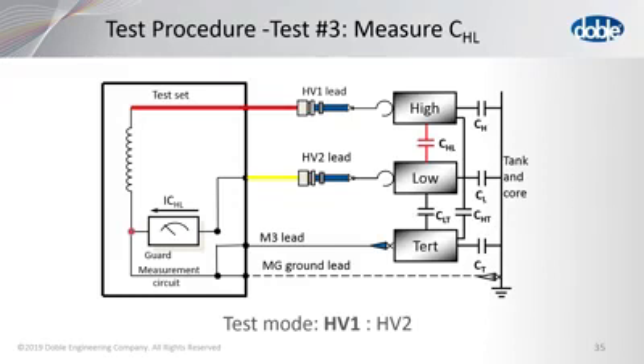Very good, thank you. Next question, is power factor an applicable test for current transformers? Yes. Of course, that wasn't explained in this webinar, but yes, we do recommend power factor testing for CTs. The test for a CT is very, very simple. You short the H1 and H2, perform a test to ground at the highest voltage that is applicable for that CT, and then we'd like to have it tested at a lower voltage also.